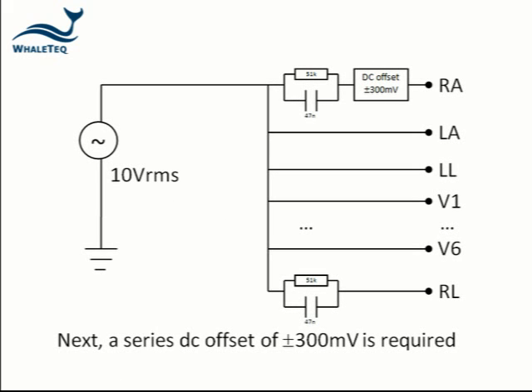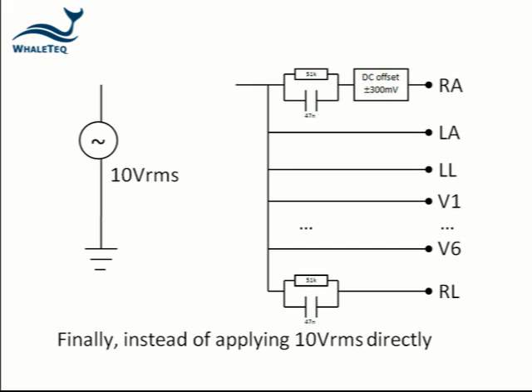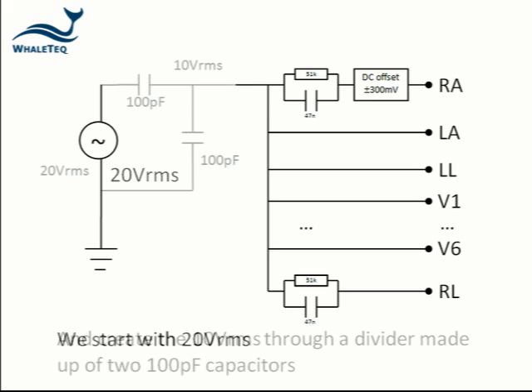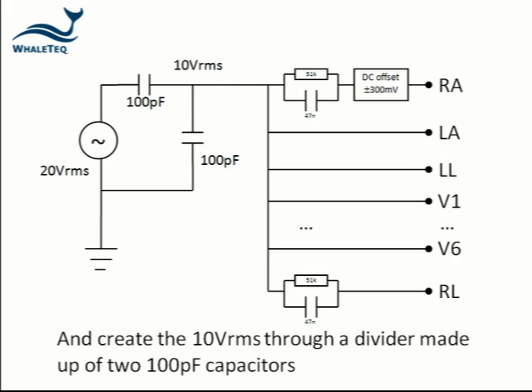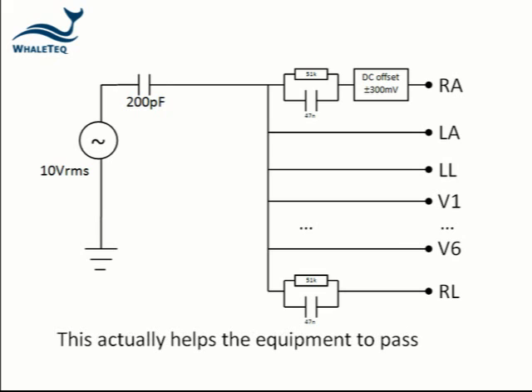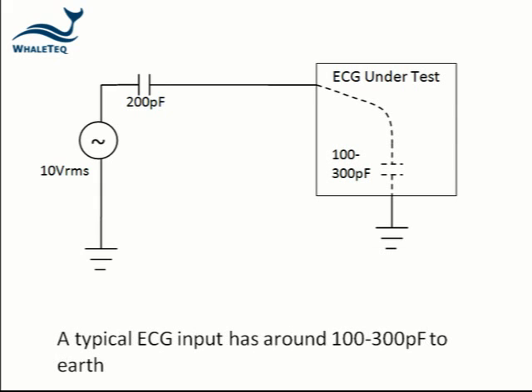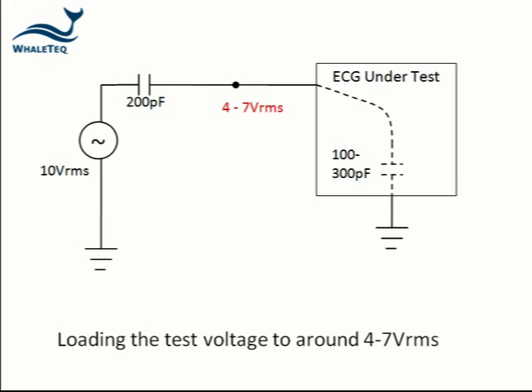Next, a series DC offset of 300 mV is added. This generally has no effect on the result, but is anyhow required by the standard. Finally, instead of applying the voltage directly, the standard requires us to start with 20 volts RMS and create the 10 volts through a divider made up of two 100 pF capacitors. This creates an equivalent circuit of 10 volts source with a series 200 pF. This actually helps the equipment to pass, as the equipment can load down the voltage during the test. A typical ECG input has around 100 to 300 pF to earth, which brings the actual test voltage down to around 4 to 7 volts RMS.